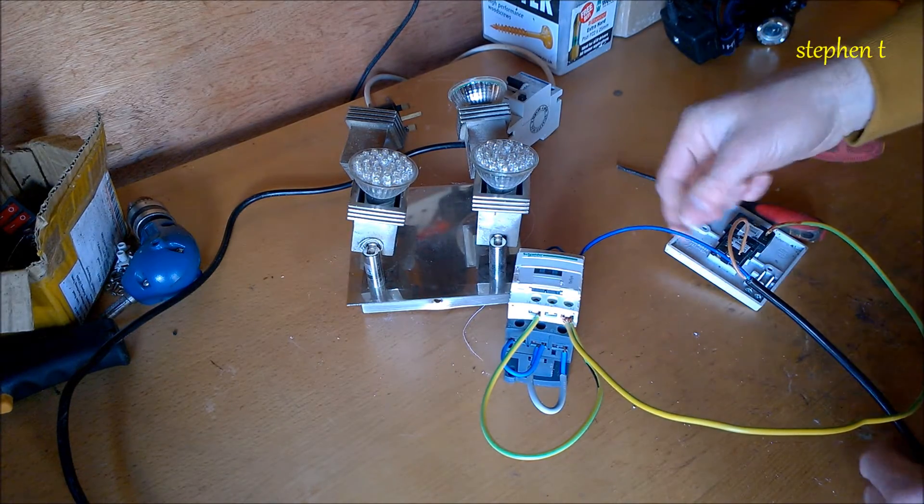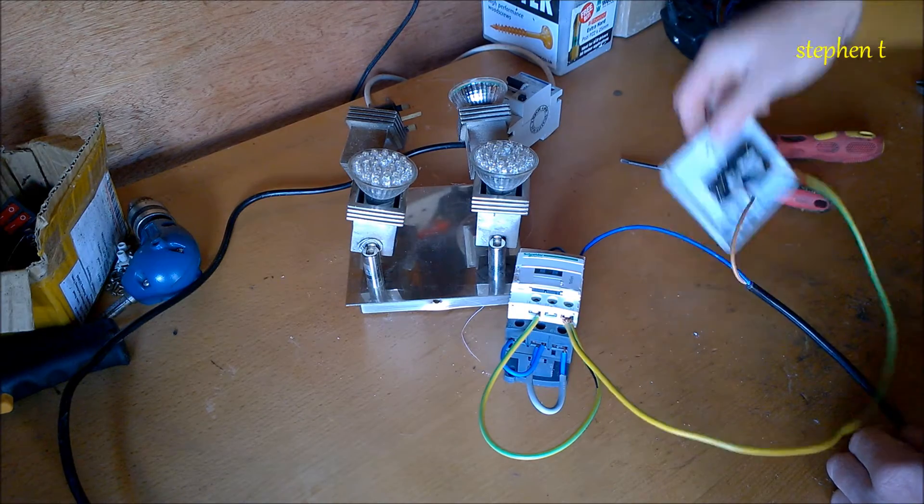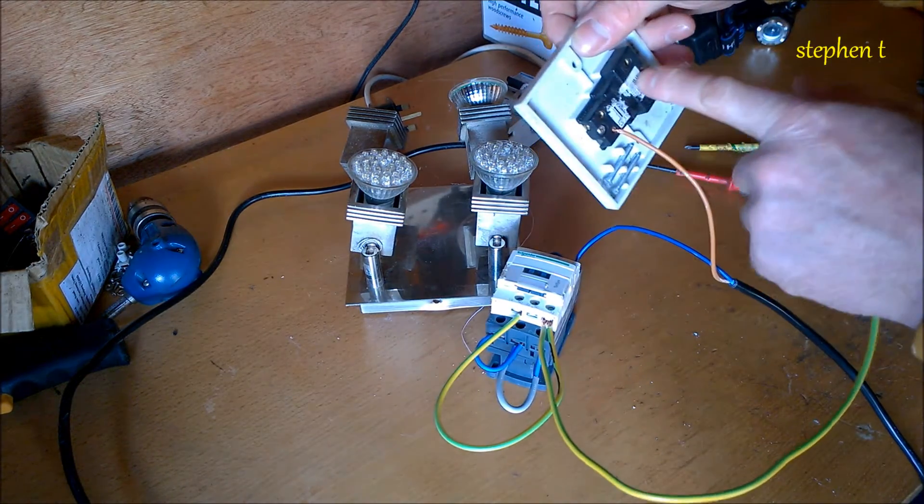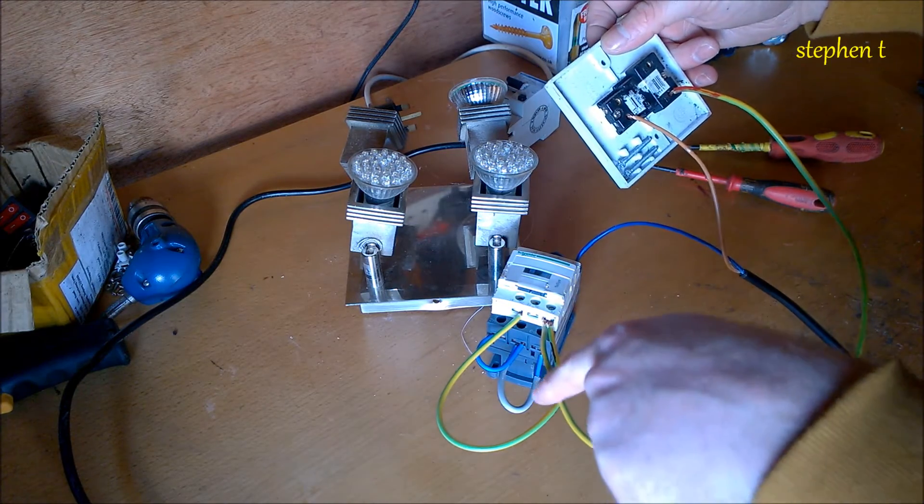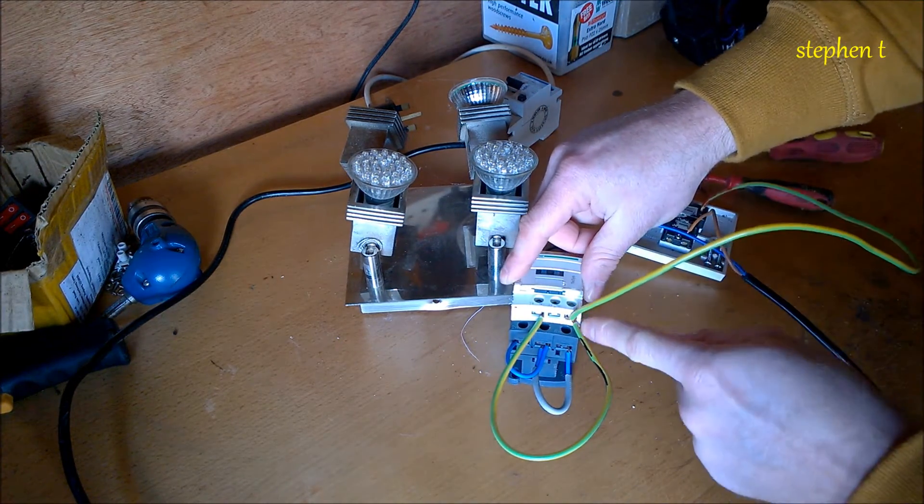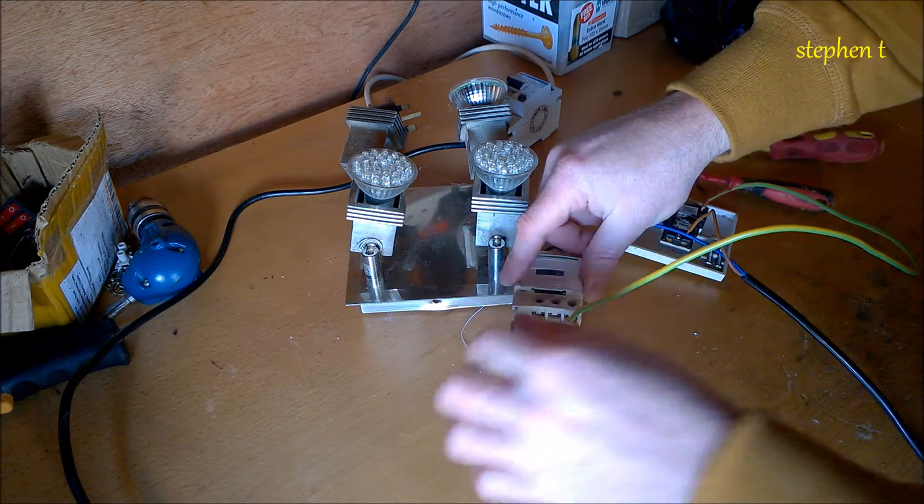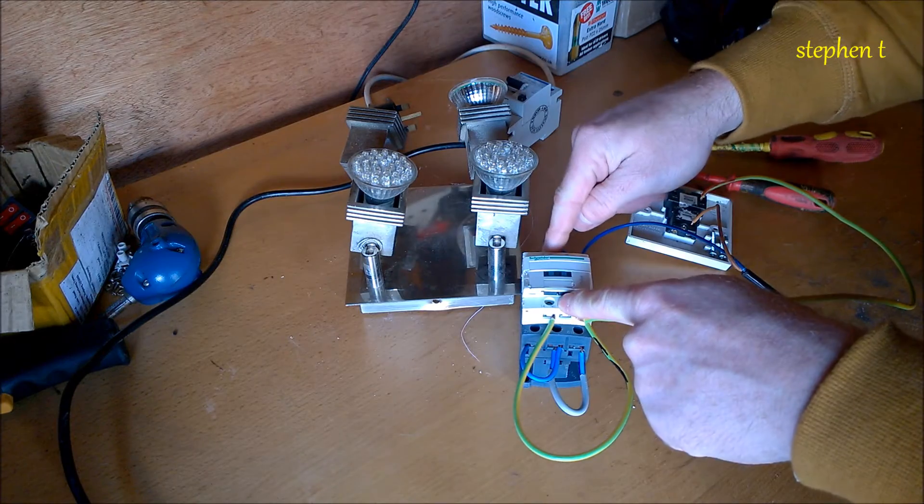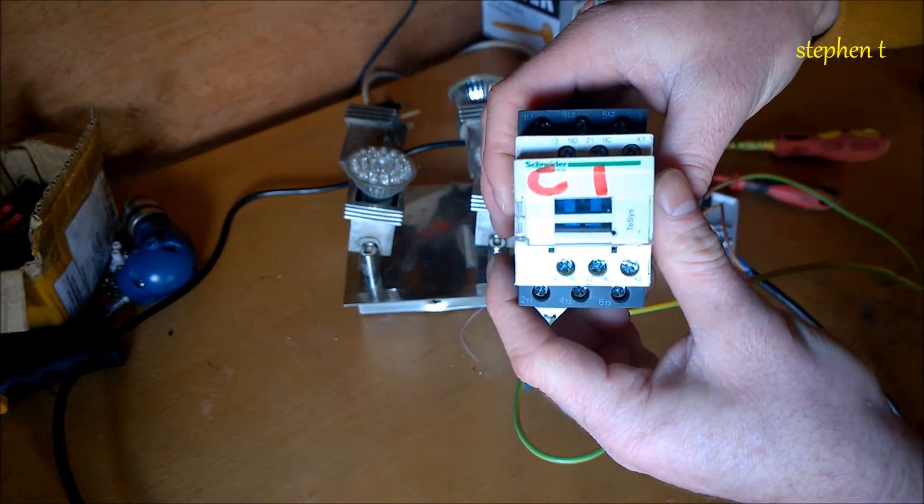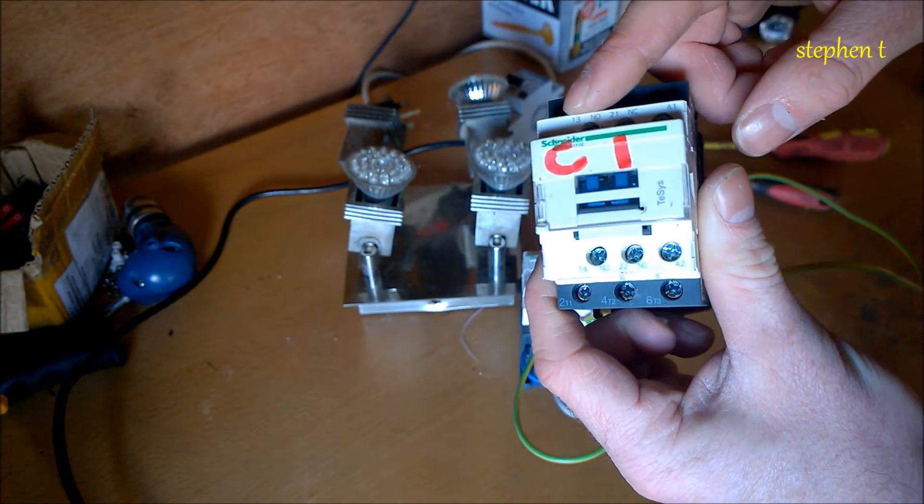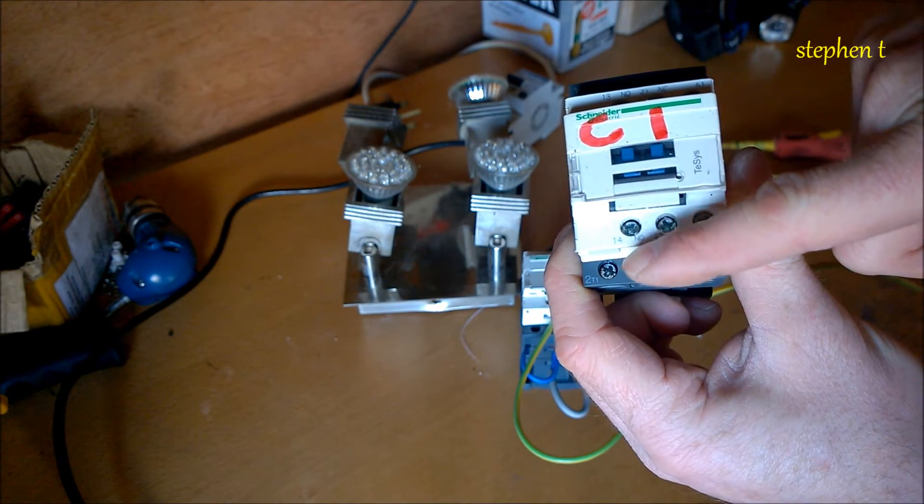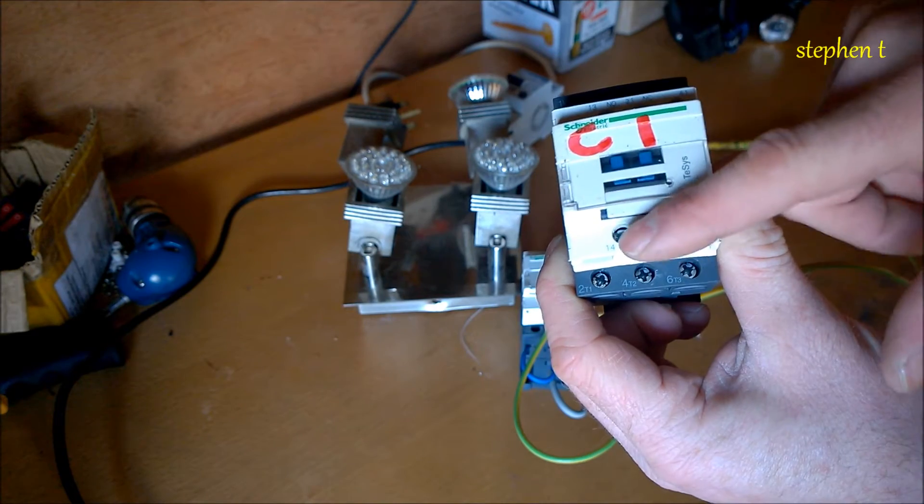Now, so you have your neutral splitting into your pilot light, your live being broke through your switch, comes through here out and into A2. So in A2, I'll bring the link over to your normally open contactor, and the same up here. A reference up here to normally open. I'll just show you better here. See, normally open, and down here normally open. So once you energize the contactor, that will close the contact inside to give you a pilot light.